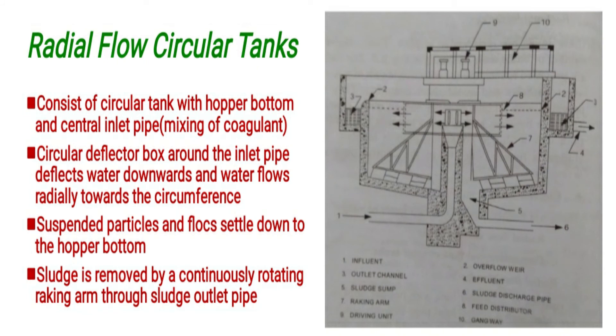It consists of a circular tank with a hopper bottom and a central inlet pipe — this is a radial flow circular tank. A circular deflector box around the inlet pipe deflects water downwards, and water flows radially towards the circumference. Suspended particles and flocs settle down to the hopper bottom.